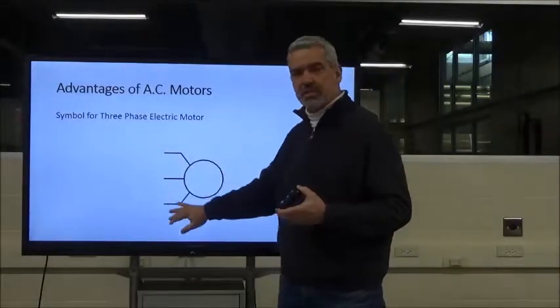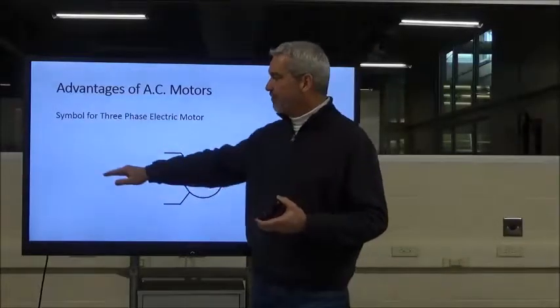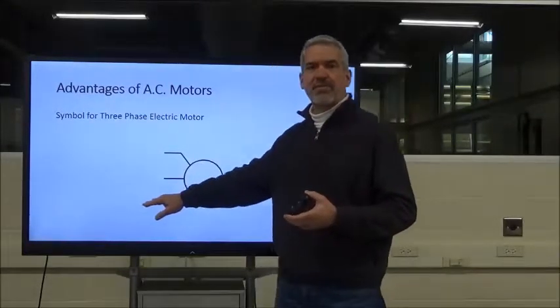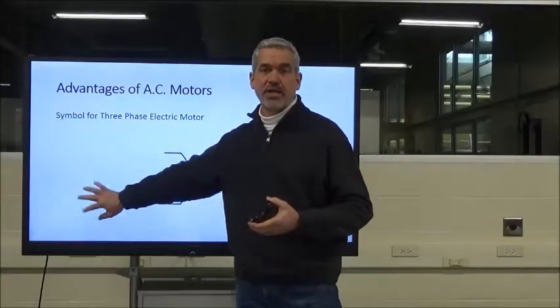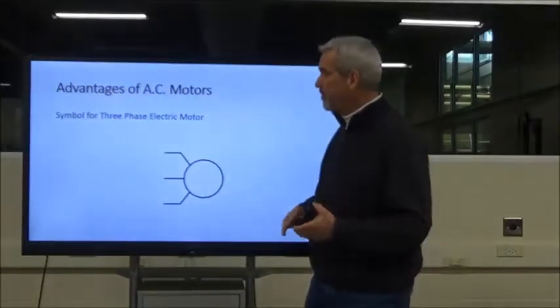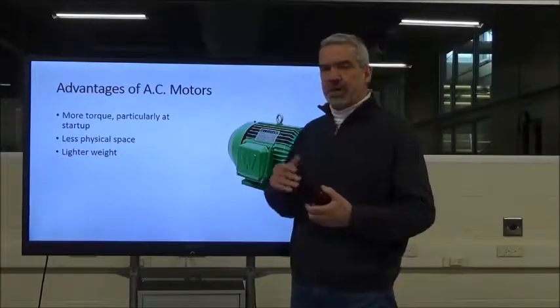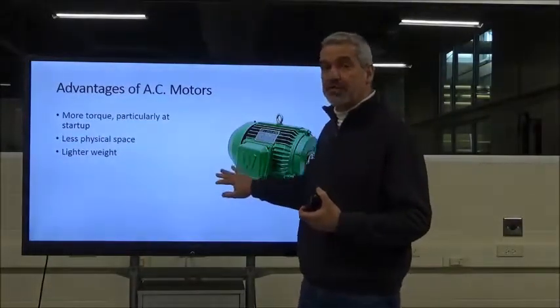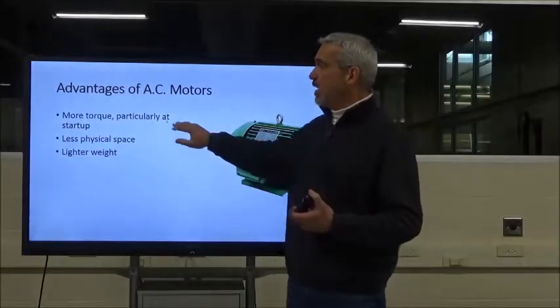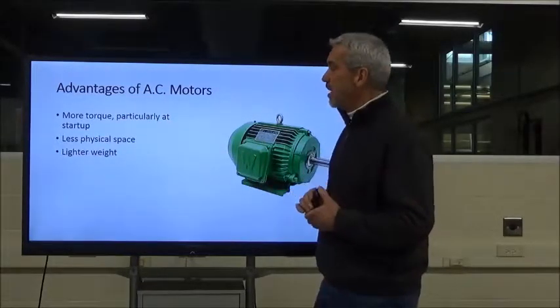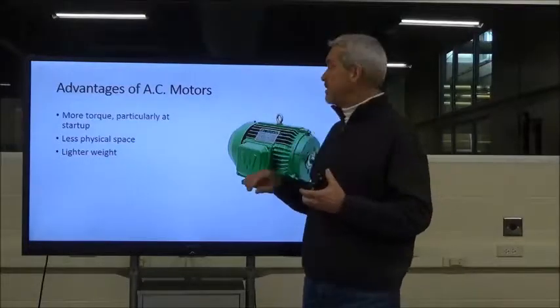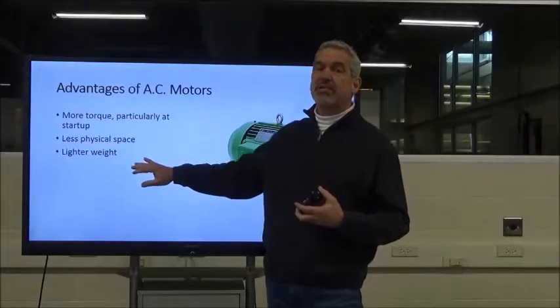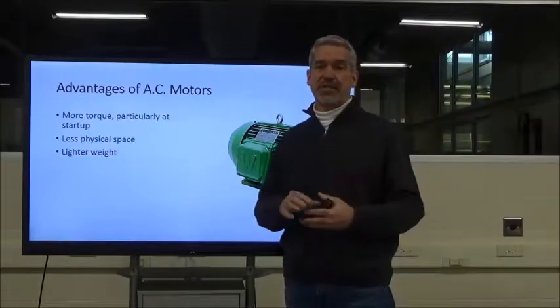This is the symbol for a three-phase motor. From our previous lecture, we had three dark lines feeding the three phases of voltage — L1, L2, and L3 — to our motor. We also talked briefly about the advantages of an AC induction motor, which we call squirrel cage motors. They have more torque, particularly at startup. They also take up less physical space — a 10 horsepower three-phase motor is much smaller than a 10 horsepower single-phase motor.